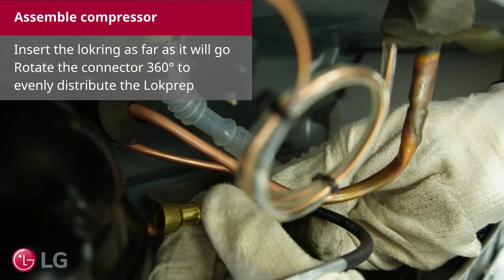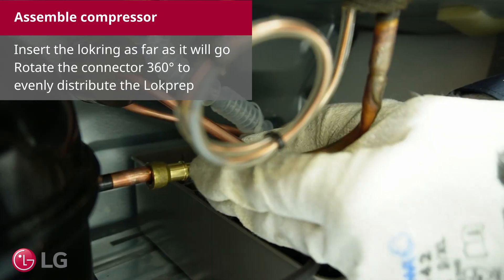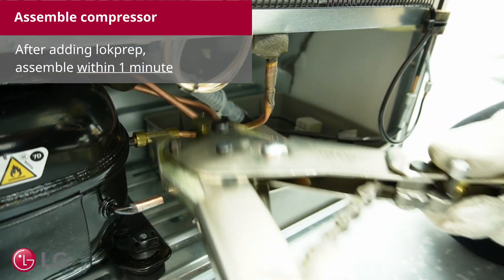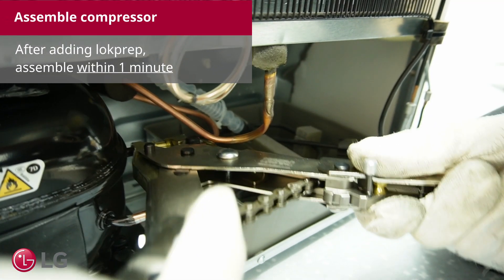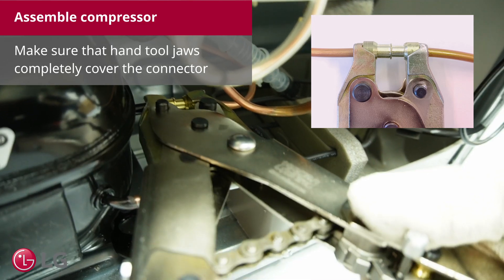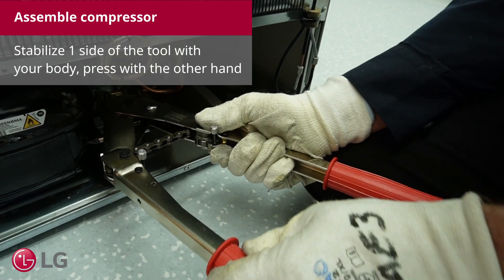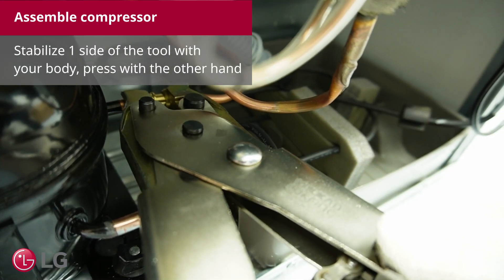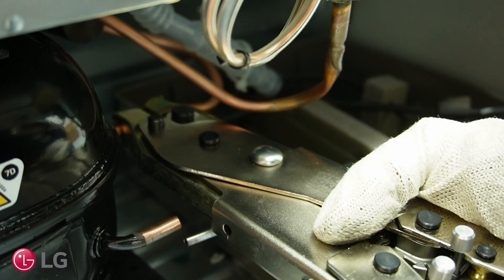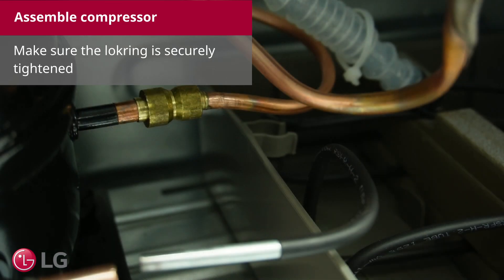Insert the Lokring as far as it will go. Rotate the connector 360 degrees to evenly distribute the Lokprep. After adding the Lokprep, assemble within 1 minute. Make sure that the hand tool jaws completely cover the connector. Stabilize one side of the tool with your body and press with the other hand. Make sure the Lokring is securely tightened.